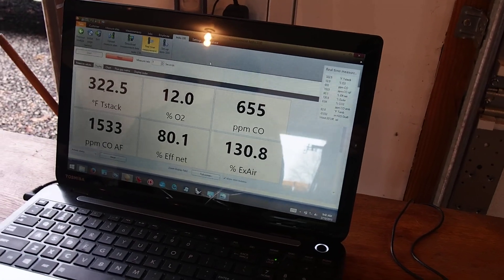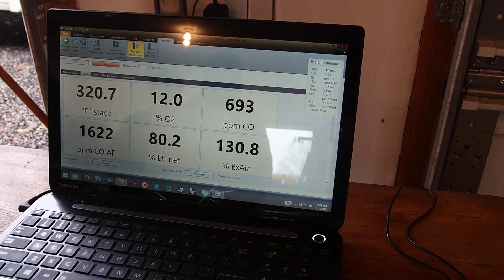Watch the O2. If the O2 starts really nose-diving, then the CO will probably... Right now, I expect if that O2 stays sort of 12-ish like that, it'll probably keep a hold of itself.